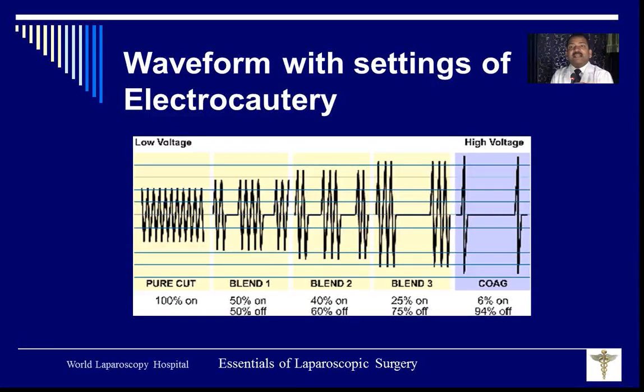the cell membrane cannot fracture. Of the 500 kHz to 10 MHz frequency range, with the blue pedal only 500 kHz comes. There is no turbulence, there is only movement. The word turbulence means uncontrolled movement, which happens in cutting. In coagulation, frequency comes only 6% of the time and 94% it doesn't. So there is a little movement of ions inside the cell, which increases the temperature. Once the temperature of the tissue reaches 55 degrees centigrade, the protein gets denatured and then it shrinks. Once the denatured protein shrinks, the lumen of the vessel gets closed.